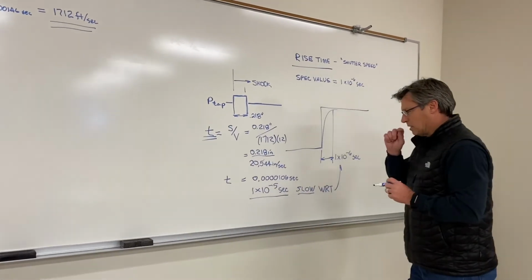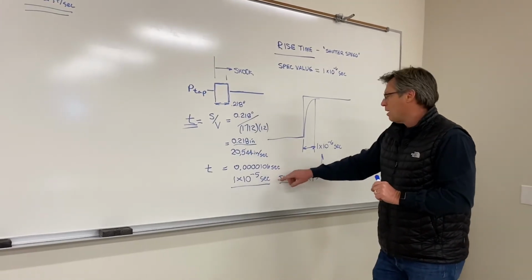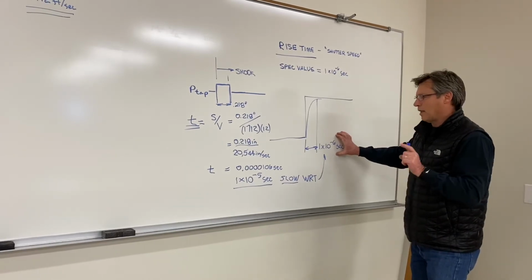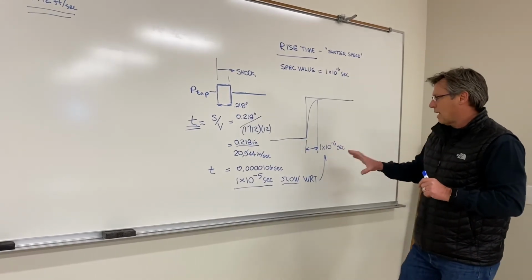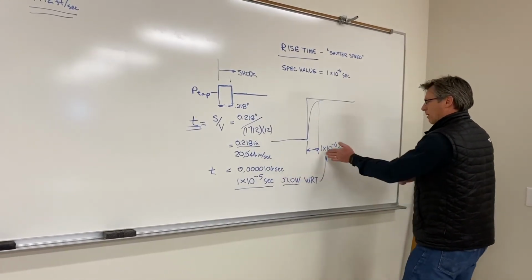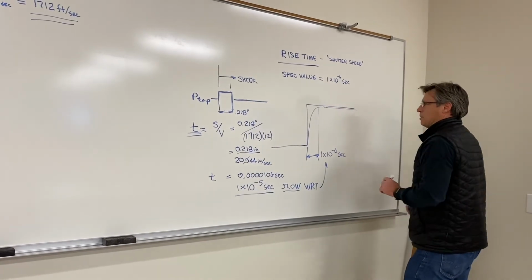Now the nice thing that we see here is that this event is relatively slow compared to the rise time, the capability of the pressure transducer. And that being the case, then we can say that this event is so much longer than the rise time of this pressure transducer that we are accurately able to capture that event.